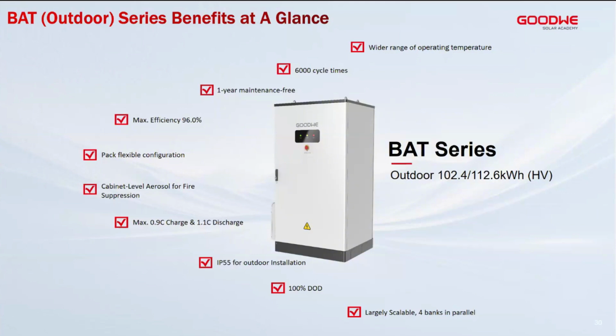So the difference with this one, now this is where the difference starts coming in. The BAT indoor will have pack level, but the BAT outdoor will have cabinet level aerosol fire suppression. Now, with the BAT indoor, we have 1C charge. The BAT outdoor will have 0.9C charge, but the discharge is the same, 1.1C for both BAT series. The IP ratings is also different.